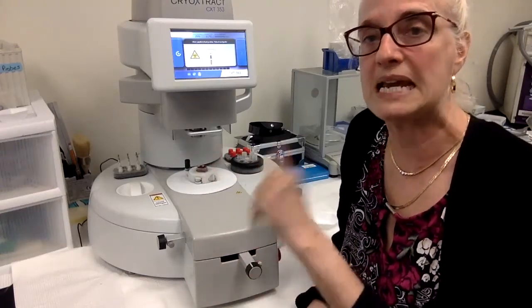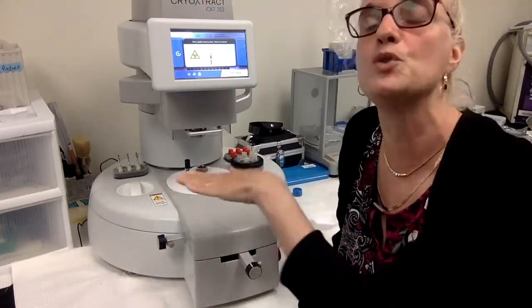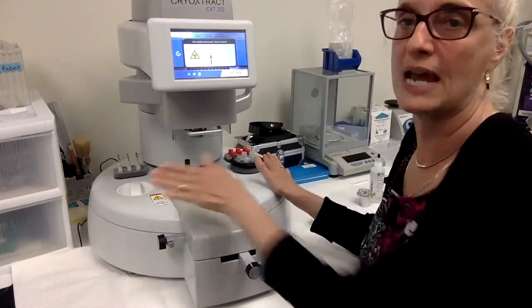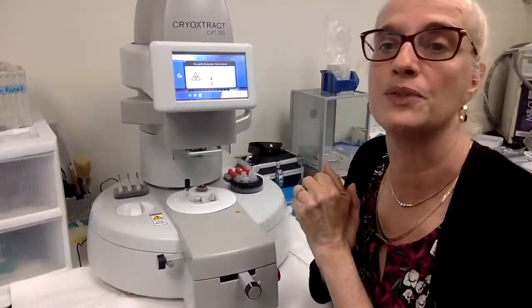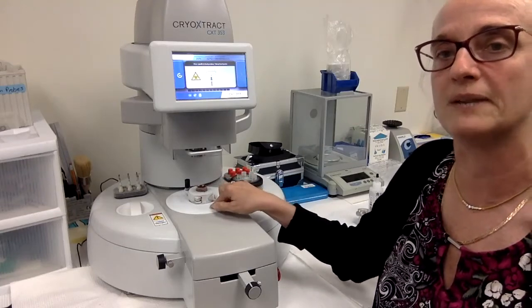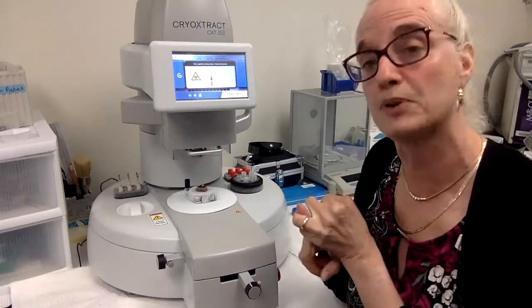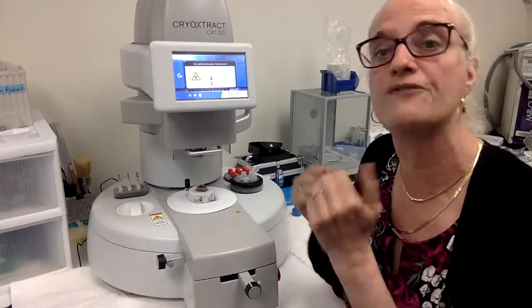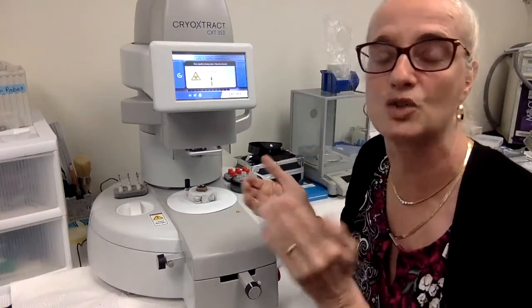At all times you know how much liquid nitrogen is in your tank. On our computer screen it will tell you the temperature that your instrument is at at all times. There is a thermocouple underneath the sample fixture — that's the fixture in the center of the instrument — that will measure the temperature. Once your instrument gets cold enough to fill up, it takes about two minutes to fill and then anywhere from 8 to 12 minutes to get to temperature.